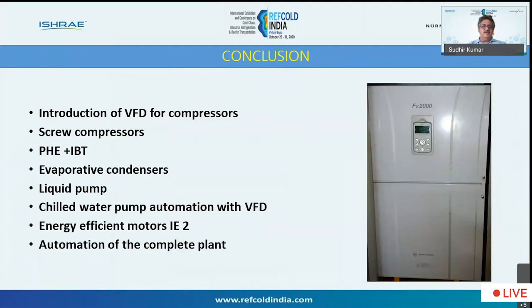But the major conclusion I would like to say is use of screw compressors in bigger dairy plants. I'm not against reciprocating compressors, but if you have a bigger refrigeration capacity, then you can use screw compressors. Otherwise, if it's a smaller plant, you can use a reciprocating compressor also with variable frequency drive, with IE4 motor and PHE plus IBT system. You should always have a combination of PHE plus IBT, because IBT will give you a little bit of safety during any power failure or even for some of your peak loads.